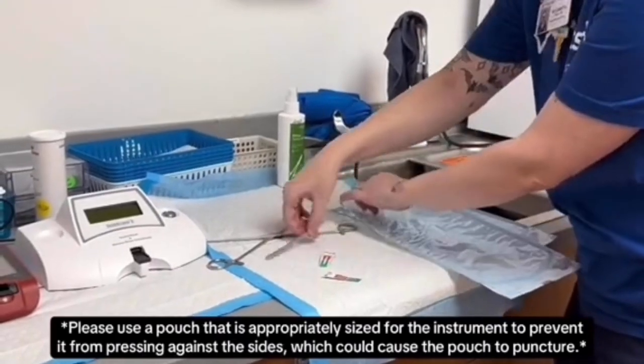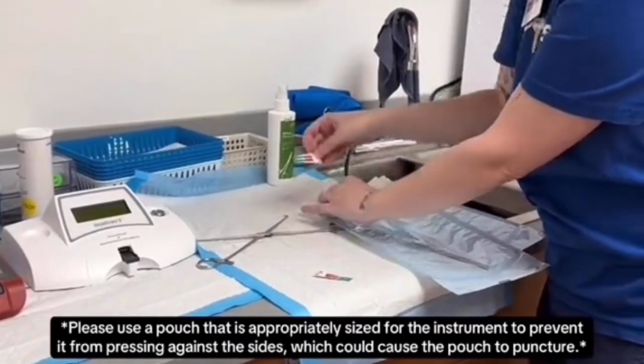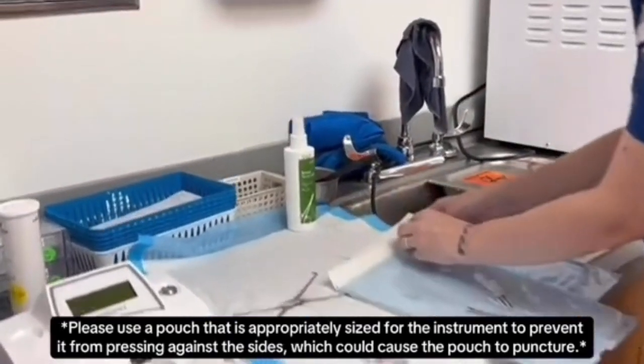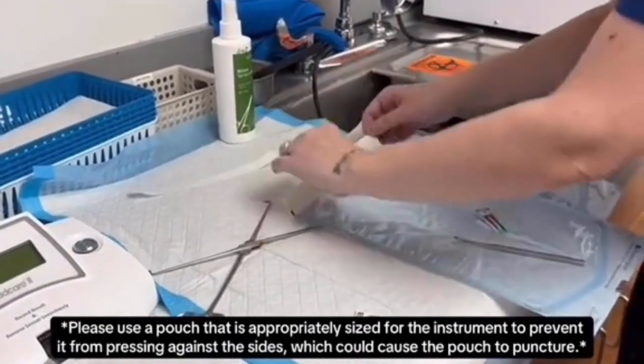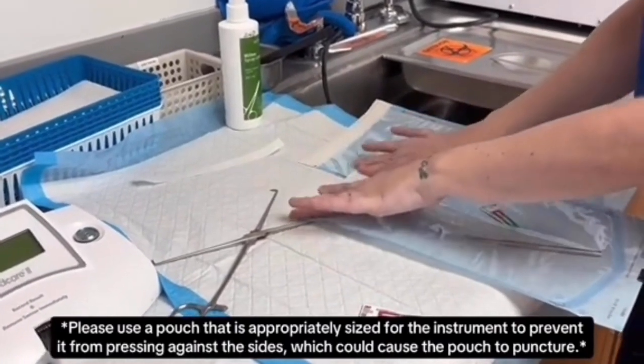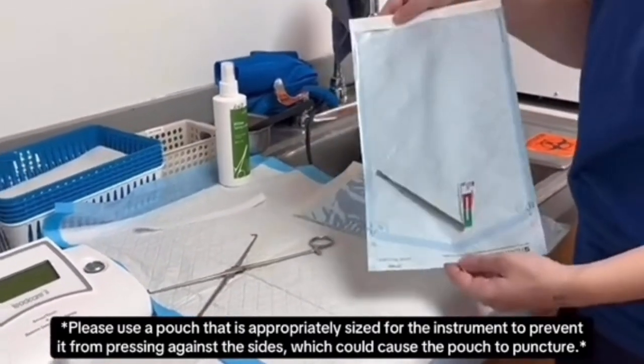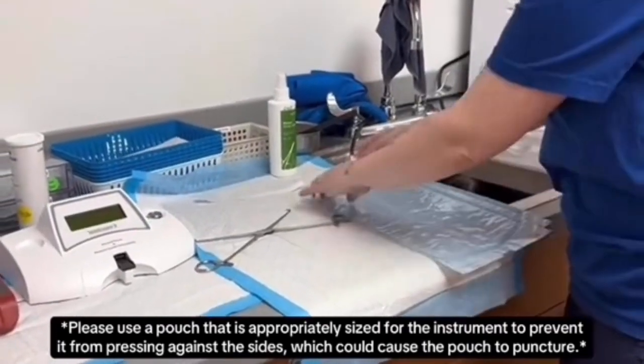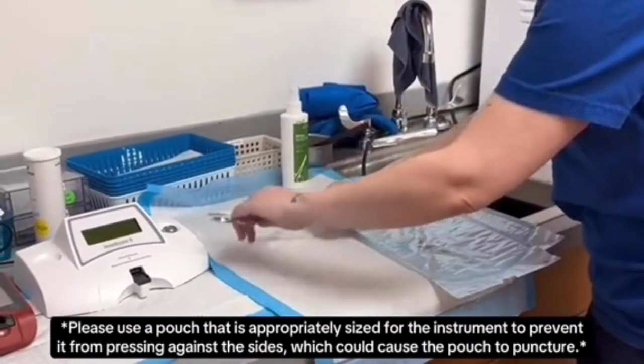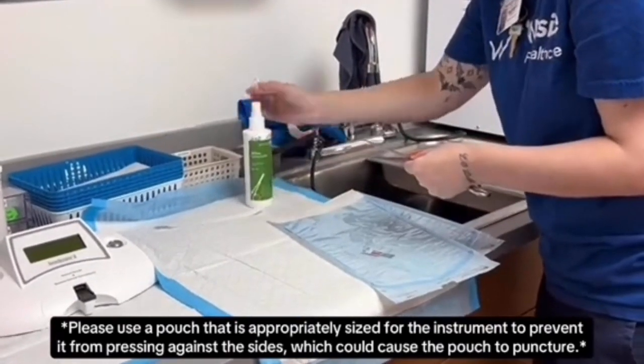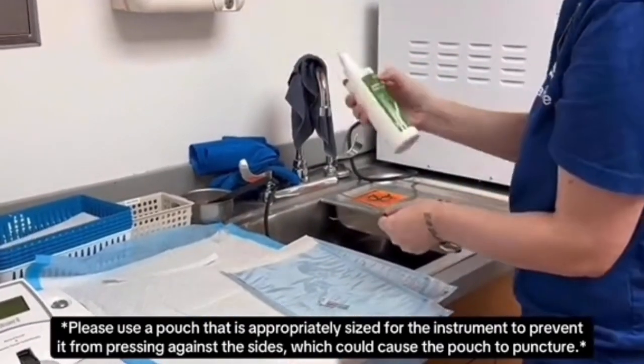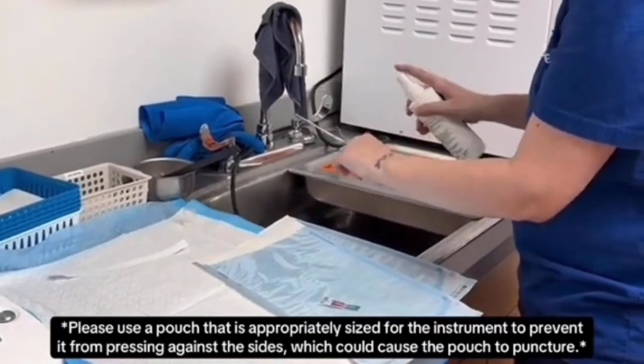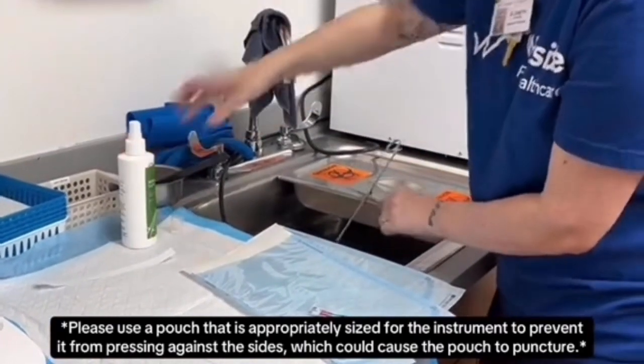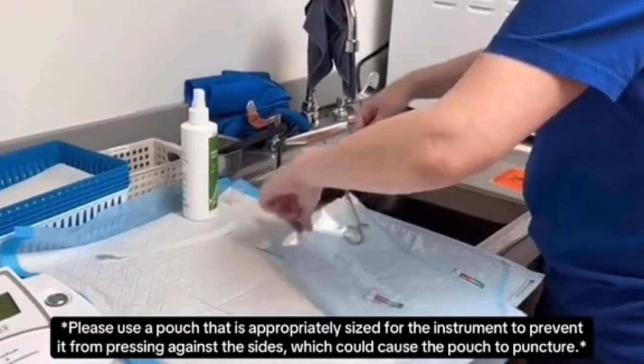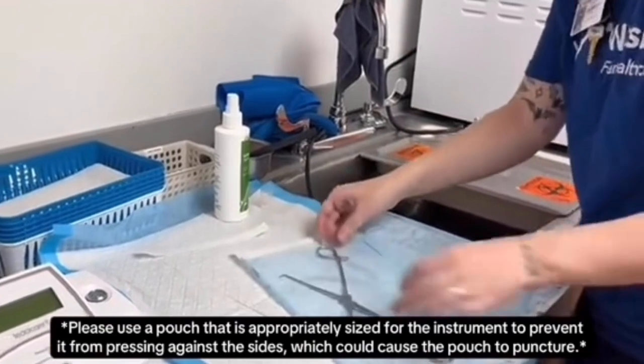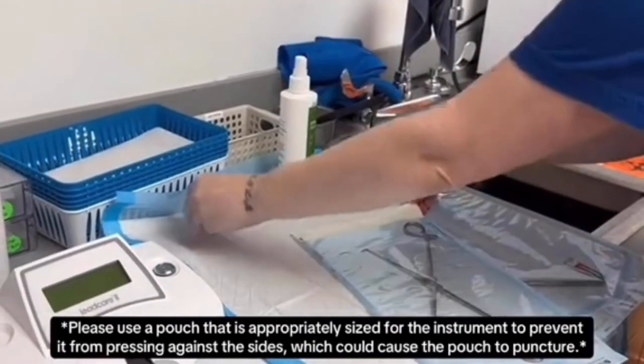Place one instrument and a chemical indicator in each self-sealing pouch. Make sure the pouch is big enough for the instrument to fit comfortably inside and the chemical indicator is facing up so you can see the results. If an instrument has hinges or moving parts, spray them with a water-soluble lubricant. Make sure you don't over-lubricate. Place an instrument with hinges in the open position and remove the backing paper and seal the pouch.